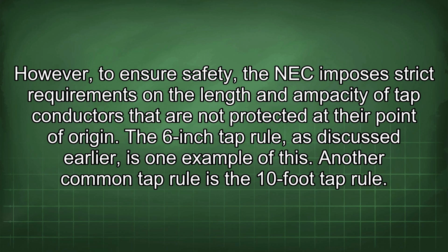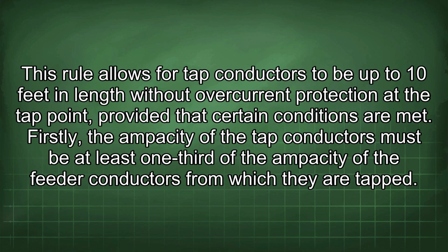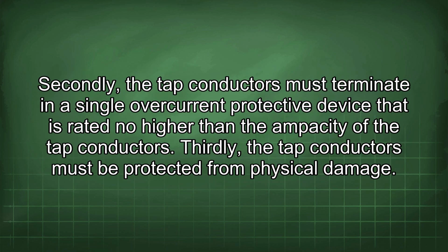The 6-inch tap rule, as discussed earlier, is one example of this. Another common tap rule is the 10-foot tap rule. This rule allows for tap conductors to be up to 10 feet in length without overcurrent protection at the tap point, provided that certain conditions are met. Firstly, the ampacity of the tap conductors must be at least 1/3 of the ampacity of the feeder conductors from which they are tapped. Secondly, the tap conductors must terminate in a single overcurrent protective device that is rated no higher than the ampacity of the tap conductors. Thirdly, the tap conductors must be protected from physical damage.